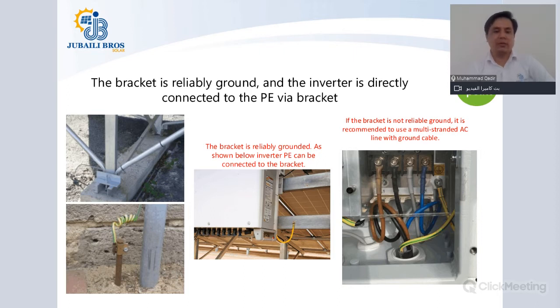The other way it could be that you are installing your inverter on a wall. In that scenario, normally people prefer to use the inside earthing point of the inverter. In this picture, you can see on the right side the earthing point, which is visible inside the maintenance compartment of the inverter. So inside the inverter or outside the inverter, you will have 2 points. Why Huawei has given these 2 points is that you can do the daisy chain of the earthing of the different inverters to each other and take one single cable from the last inverter to the grounding point inside your LV panel. So now you have the two options: either you use the inside earthing point or the outside, and you can install your inverter in different scenarios.